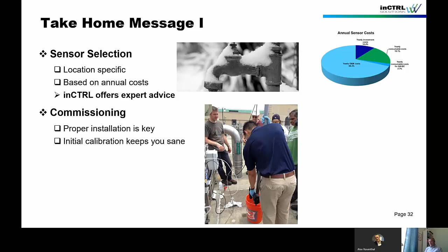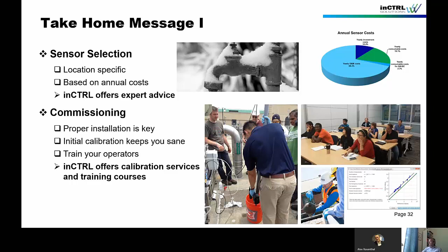Commissioning. So proper installation, I think I showed that, is key. What we highly recommend is that initialization phase where you make sure that the sensor is properly working right in the beginning, and only after you pass that step you go into normal operation. Really, that keeps you sane instead of tweaking. Training of your operators is also very important. We offer that as training courses. We do a lot of hands-on and classroom settings, and we also can support you in calibration of your probes, that base calibration or initialization. Yeah? And we also have the software in place to support that.